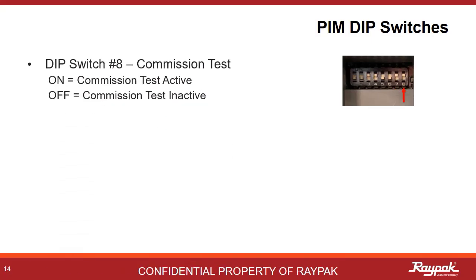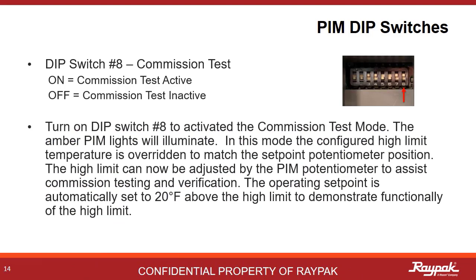Dip switch number eight controls the commission test. This is a handy tool for demonstrating that the high limit is working properly. With dip switch number eight on, the boiler will run to 20 degrees higher than the high limit to force a high limit shutdown. Once complete, power off the boiler, turn off dip switch number eight, then turn the boiler on and clear the fault.